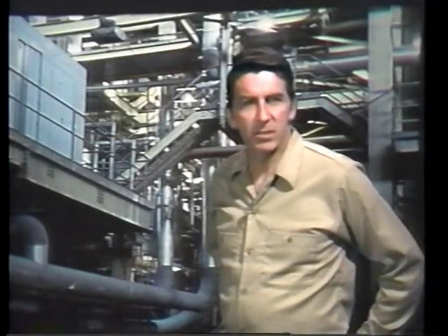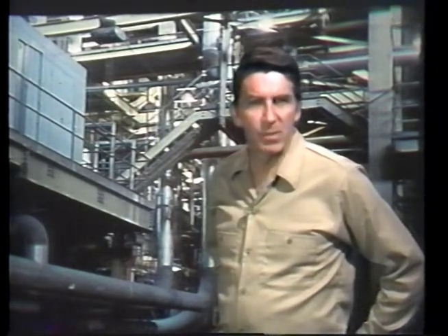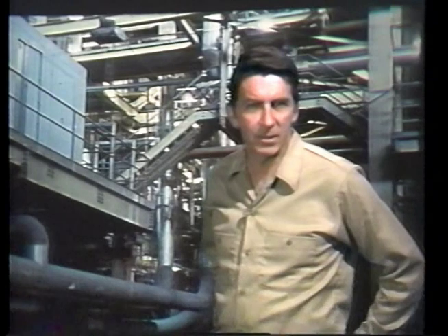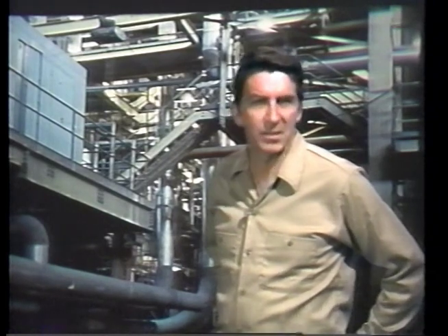So far, we've discussed thermostatic and mechanical traps. Thermostatic traps, you remember, operate by sensing the temperature difference between steam and condensate. Mechanical traps, on the other hand, rely on the density difference between steam and condensate. And now, we'll discuss thermodynamic traps. We'll see how they operate, and we'll talk about some of their more common maintenance problems.